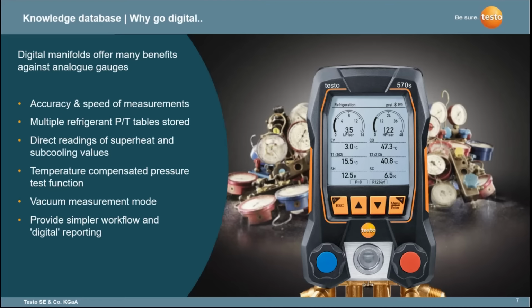Now, the other side of this ability to store refrigerants is the future-proofness of a digital manifold. As new refrigerants come out, and we're all aware that the refrigeration market is changing and ever evolving with moves towards lower GWP refrigerants, those refrigerant tables can be easily updated and added into the instrument. There's no way the instrument becomes obsolete because it can't work with those refrigerants.